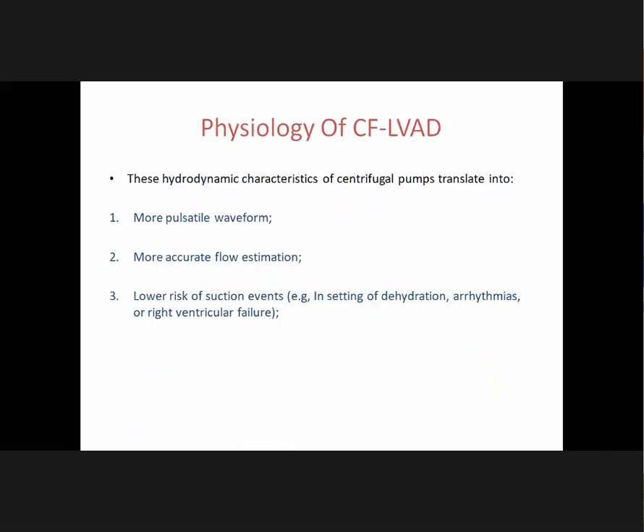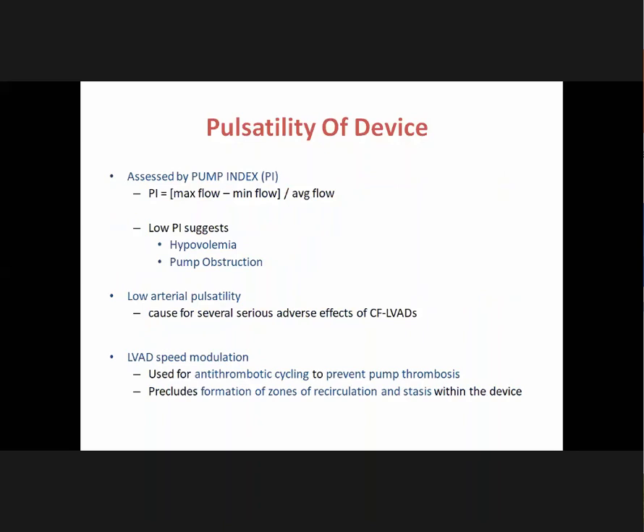Physiology of continuous flow LVAD: the hydrodynamic characteristics of centrifugal pumps produce a more pulsatile waveform, more accurate flow estimation, and lower risk of suction events in settings of dehydration, arrhythmias, or right ventricular failure. Pulsatility is calculated as the pump index — maximum flow minus minimum flow divided by average flow. A low pump index suggests hypovolemia or pump obstruction. Low arterial pulsatility is associated with several serious adverse effects. Speed modulation is used for antithrombotic cycling to prevent pump thrombosis and prevent zones of recirculation and stasis within the device.